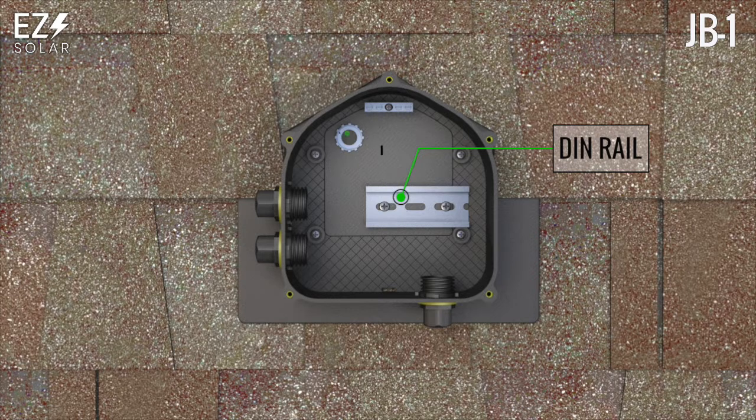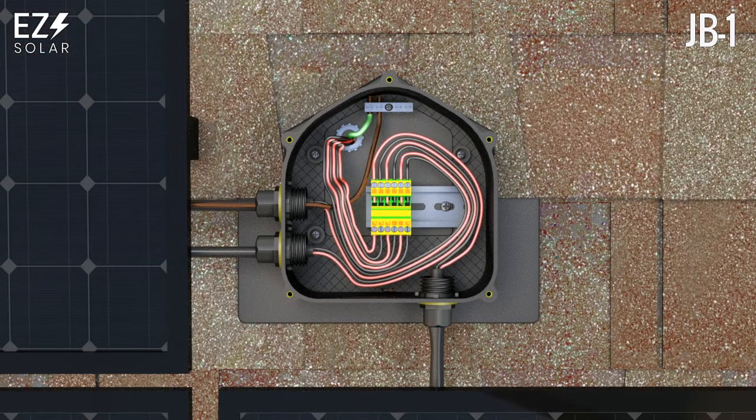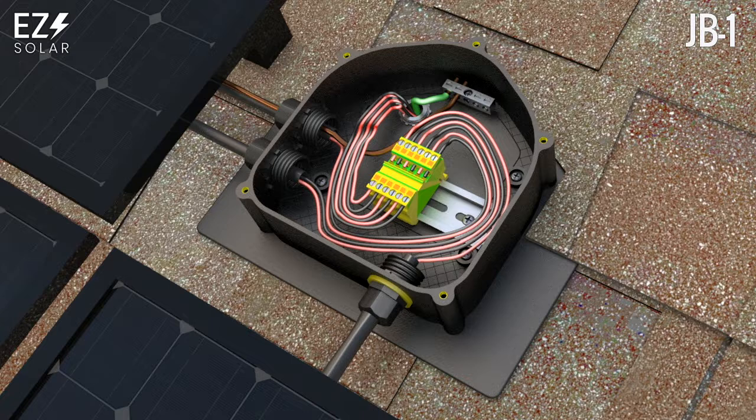At a minimum, maintain a half inch gap between the DIN rail and the ground bar. Terminal blocks can be simply wired in place, or wired outside the box and clipped onto the DIN rail, similar to installing a breaker.